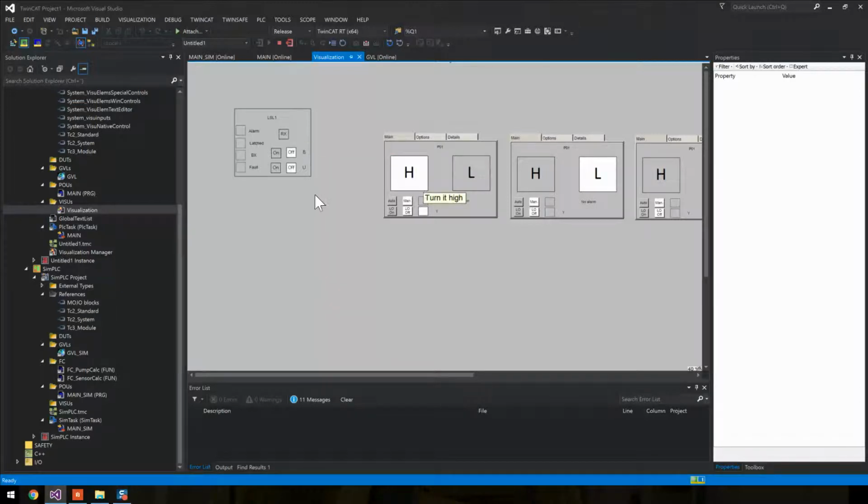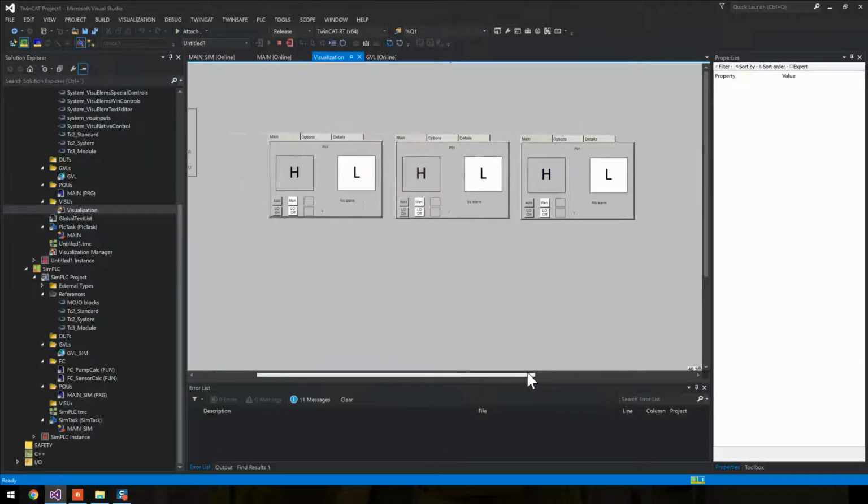Let's try and run this one. There's the alarm, and it goes off. You can reset it and start again. And there's the alarm. Reset it. And now we basically program the basic function of the 3 pumps. We can turn it off and on from the HMI screen. We can also go into outside mode.